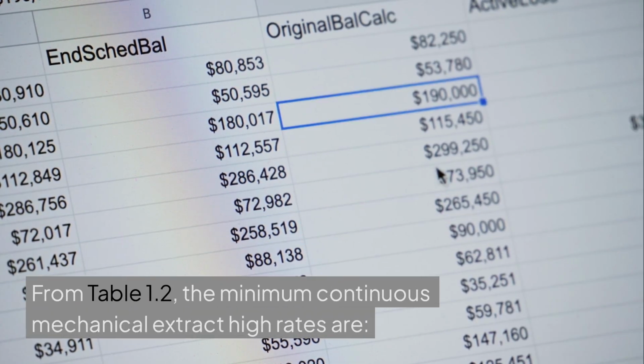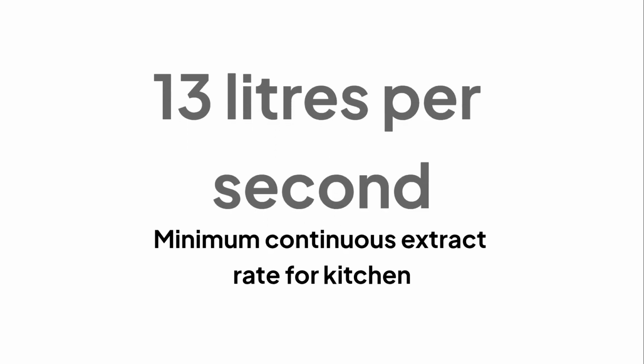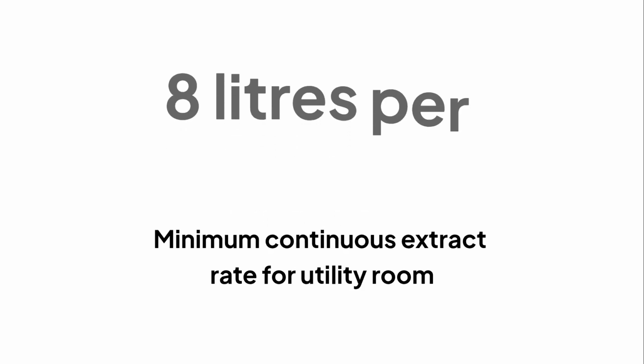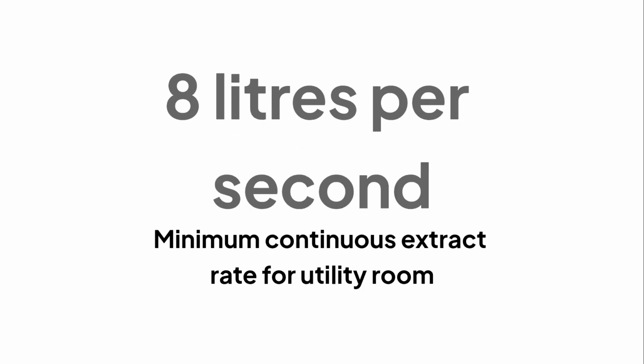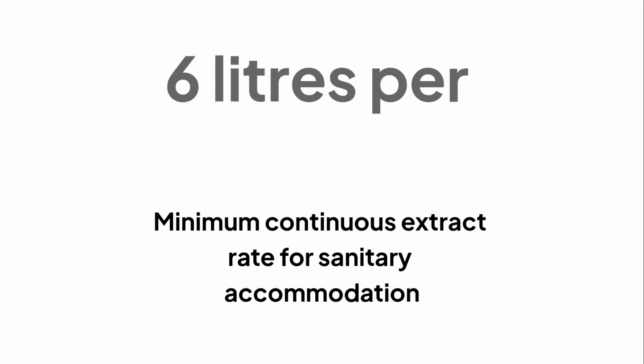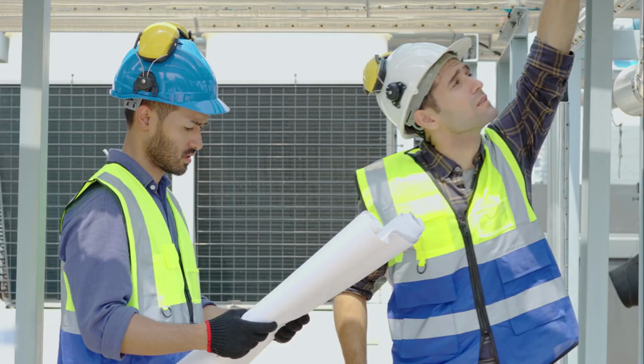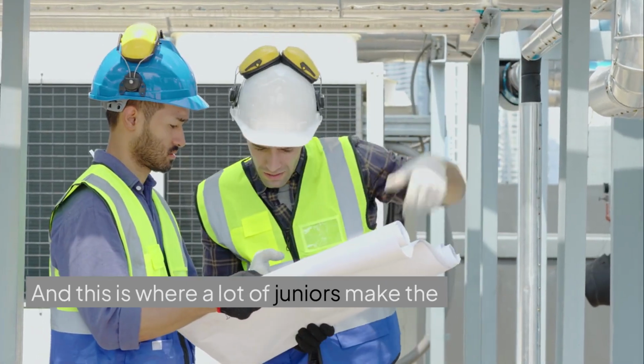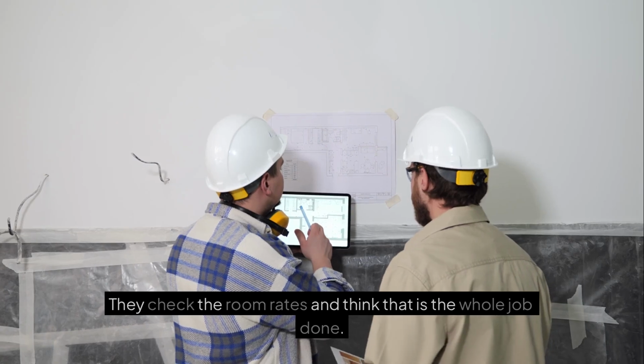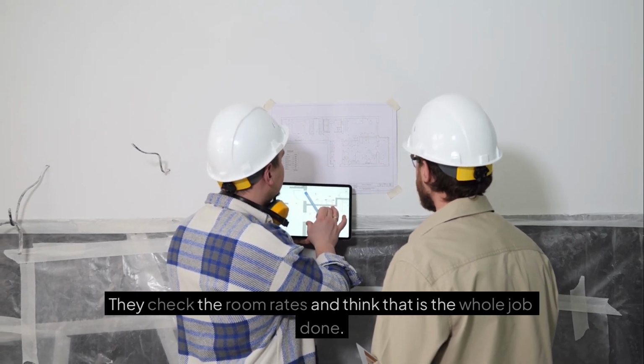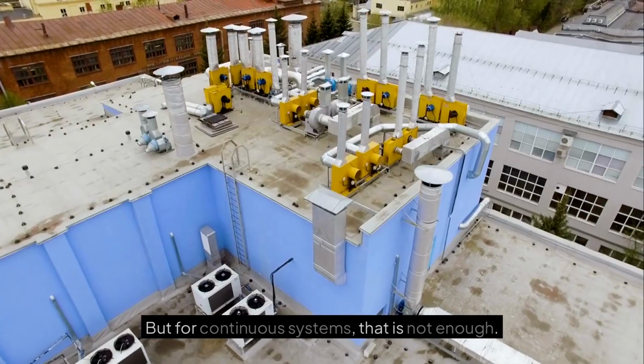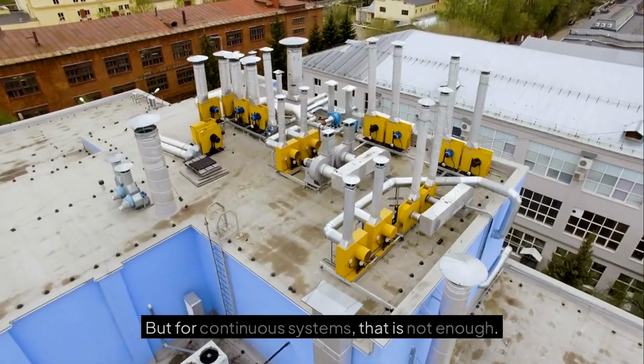From table 1.2, the minimum continuous mechanical extract rates are 13 litres per second for a kitchen, 8 litres per second for a utility room, 8 litres per second for a bathroom, 6 litres per second for sanitary accommodation. And this is where a lot of juniors make the next mistake. They check the room rates and think that is the whole job done. But for continuous systems, that is not enough.